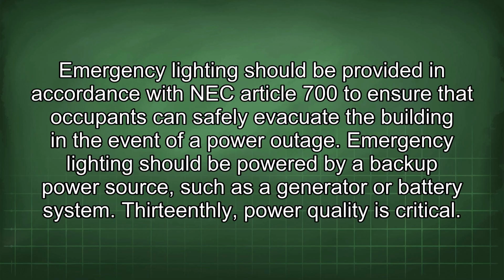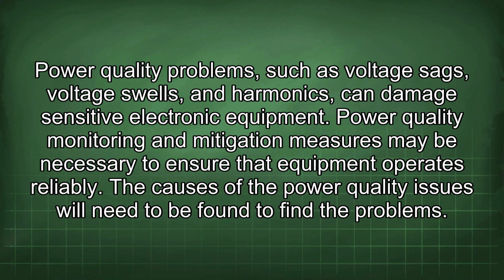13thly, power quality is critical. Power quality problems such as voltage sags, voltage swells, and harmonics can damage sensitive electronic equipment. Power quality monitoring and mitigation measures may be necessary to ensure that equipment operates reliably. The causes of the power quality issues will need to be found to fix the problems.